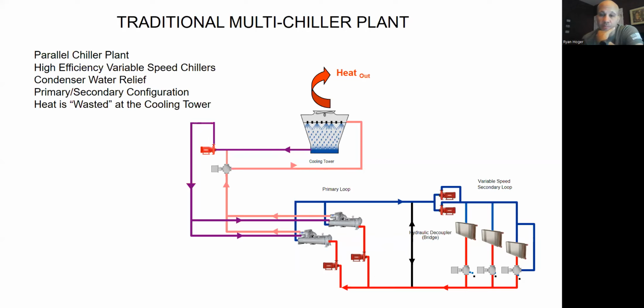Right? So when they turn on, they suck some of the water this way. If they're off, the water just goes around the loop because this circulator is pulling the water back in. But if these guys turn on, either one of them, instead of the water going down this bridge, it goes out to the building, right? This primary loop is just in the mechanical room, right? It's short. It's like 30 feet long. And then the rest of this is hundreds of feet long. That's a pretty common scenario for both chillers and boilers to have that primary, secondary.